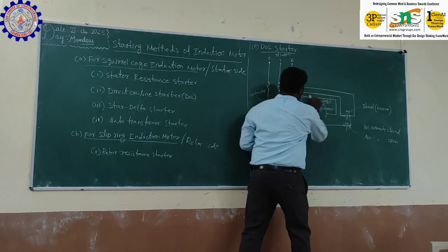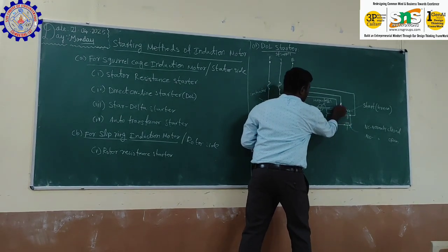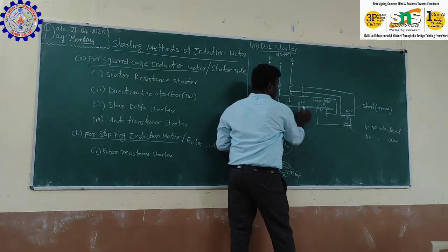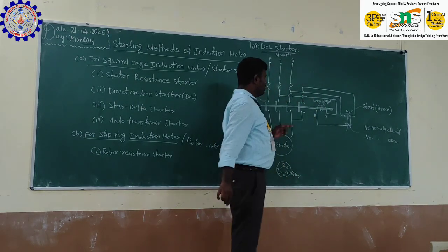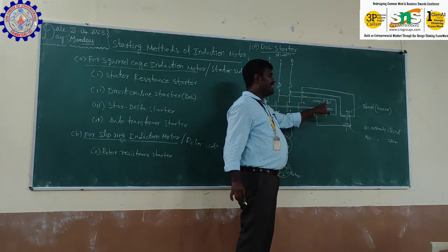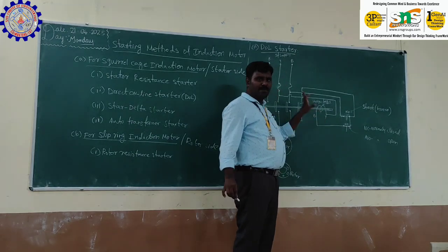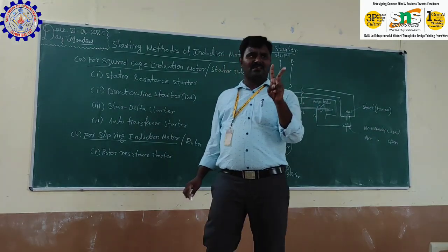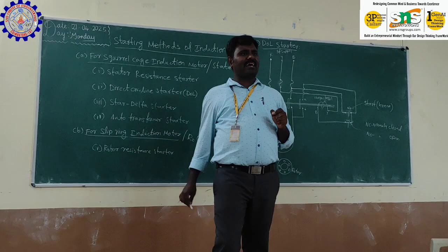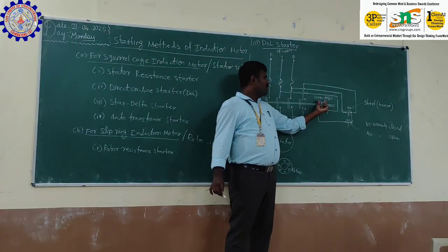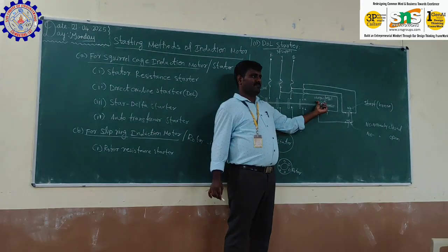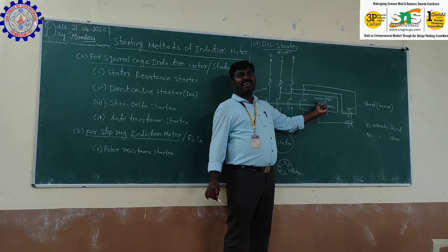இப்போ இந்த சைடு முன்னாடி open ல இருக்கு. இப்போ இந்த சைடு connect ஆயிட்டா எந்த phase connect ஆயிருக்கு? B phase. Now the magnetizing coil is connected across Y phase and B phase. Across two phases க்கு நடுவுல ஒரு magnetizing coil connect ஆயிருக்கு. Now the magnetizing coil will get energized. Magnetizing coil is getting energized.